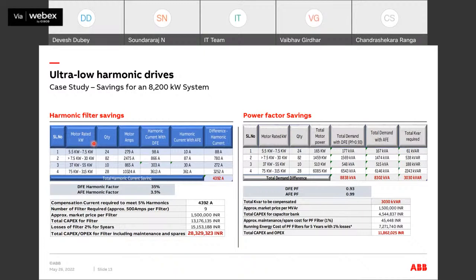This was the load which was distributed along the different kilowatts from 5.5 to 315, and various quantities were there. We have calculated the motor amps, and we have calculated the harmonic current driven by a diode front-end drive, and the harmonic current driven by an active front-end drive. When you see a diode front-end drive, the harmonic factor will be 35%. As I explained earlier, the DFE, diode front-end drive, will have harmonics up to 35%, while if you are using an active front-end drive, it can come down to 3.5%.